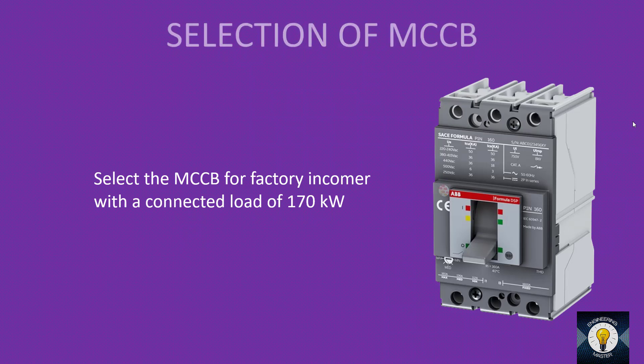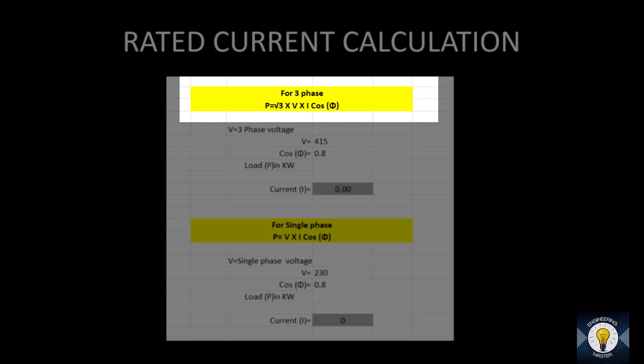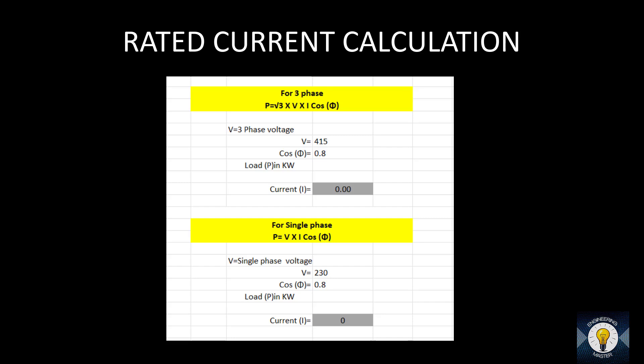The first step is calculation of rated current. For this, I have prepared an Excel sheet you can download from the description. The equation for three-phase power is P = √3 × V × I × cos φ. The power factor cos φ is 0.8, and the standard three-phase voltage V is 415 V. Entering the load of 170 kW into the Excel sheet, the current comes out as 295.98 — approximately 296 amperes.